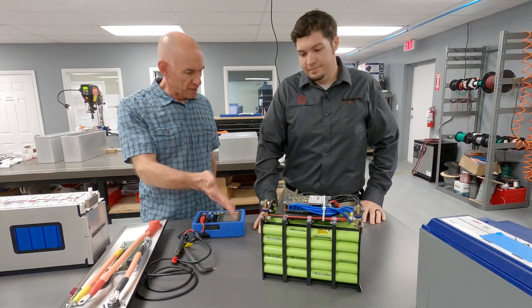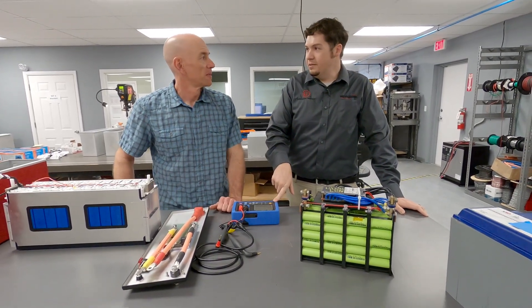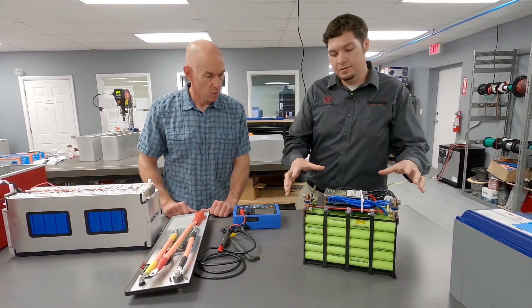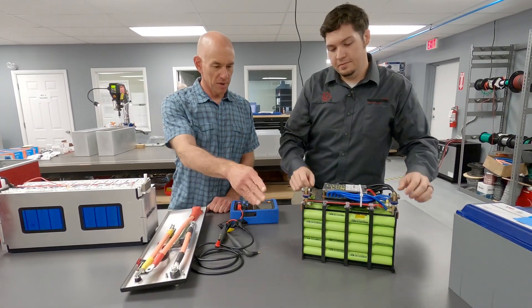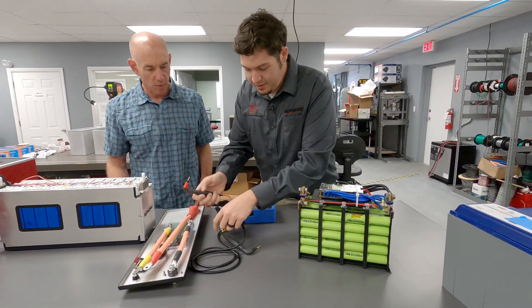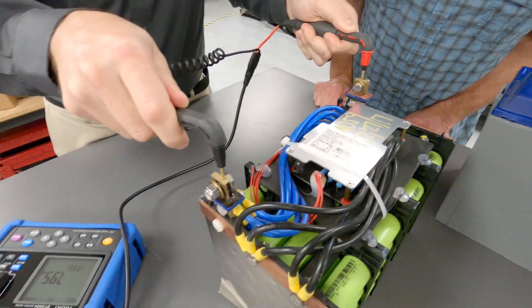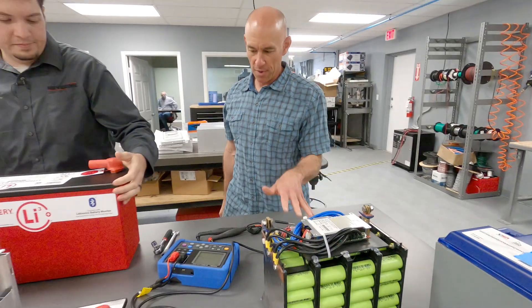At the end of the day this will deliver power, and we've got a battery tester here that gives a very accurate battery resistance using a one kilohertz impedance sine wave. This measures the internal resistance of the whole assembly — not just the lithium core, but also as it flows through the BMS to the point where you're actually connecting. Any places where it's not torqued down or a weld is missing — that's going to affect it. So let's put this on the competitor battery and see what reading we get.